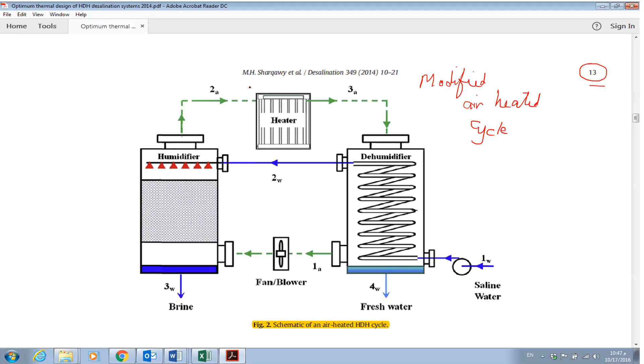This hot air effectively heats the water, and the hot water enters here and is sprayed, heating the incoming air. We're talking about air being heated to about 80 to 90 degrees centigrade, which might heat the water to about 60 degrees centigrade. So water at 60 is sprayed, and air at about 30 degrees enters here, so the air ends up being heated and humidified in the humidifier.